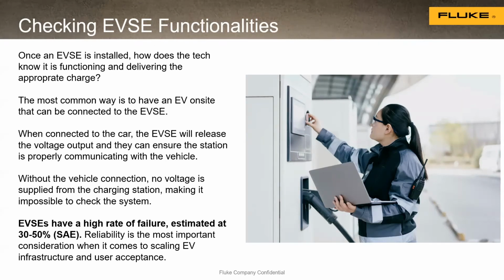Potentially, if the load was there and you could handle it. But if you put in, say, six charging stations in a row, chances are you'd have to step that up. That could run around $15,000 depending on what's needed for the transformer, the man hours and labor to hook it up and install it — whether it's underground and they have to trench systems, or overhead to the charging station. A lot of that is now put in the ground, trenching it in, bringing it down the pole line depending on the main grid, then bringing it in. So price-wise, I'm estimating, but it could easily be five digits just to bring that type of system in. But like you mentioned, Anthony, it's specific to the design and application of where they're doing it.